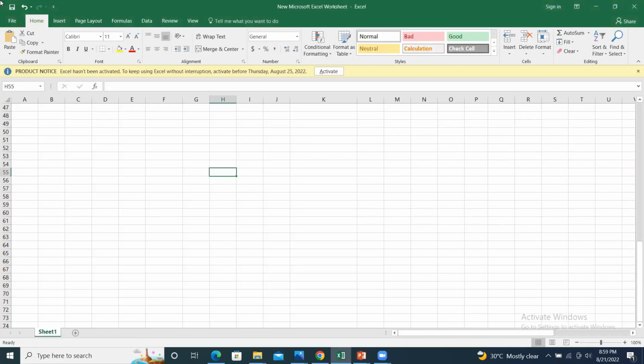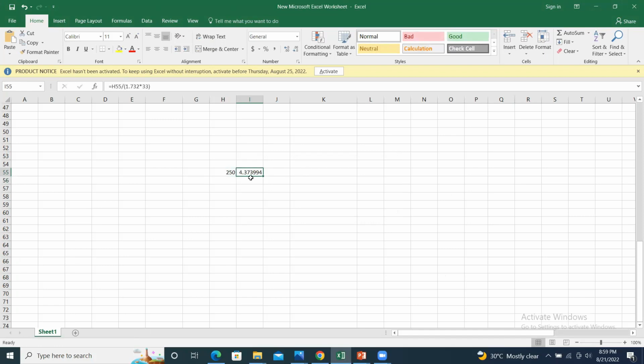Let's see, for the 220 kV system, 220, what is the one? 250 kVA. If I am converting the current, divided by 1.732 into 33 kV, kVA, no need of power factor. So what is the current? 5 amps current. Only 5 amps current in 33 kV. So in the market, we have to check whether a 33 kV, 5 amp CT is available. Nowhere is a 5 amp CT available in the market. And a 5 amp breaker is also not there at 33 kV.